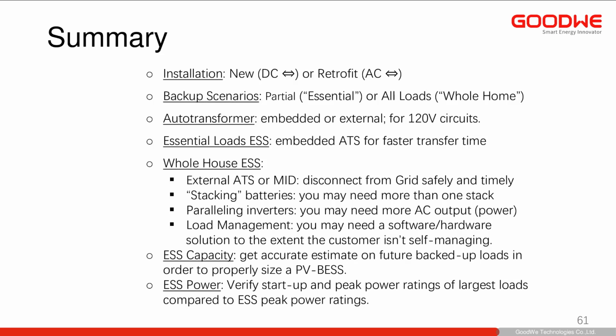Do you have an ESS for an essential loads panel with an embedded ATS for fast transfer time? If it's under 10 milliseconds, that's UPS level speed, and your load should stay alive, so you don't have to worry about restart times. If you're doing whole house, you need some form of disconnect from the grid, both safely and timely.